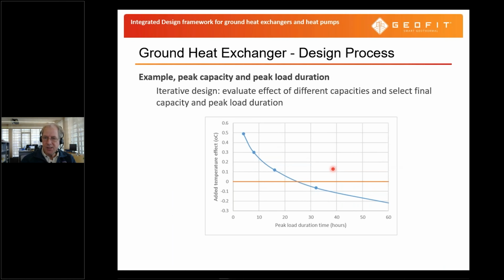Another example in the design process is to take a look at how robust the quality of our design is. Often we have things like the peak load duration. So we're looking at the capacity, but also how long that capacity has to be supplied continuously. If in the design we take a small number of hours for the continuous peak load duration, and in the operation of the building the peak load is much longer than we anticipated, we get a big change in temperature.